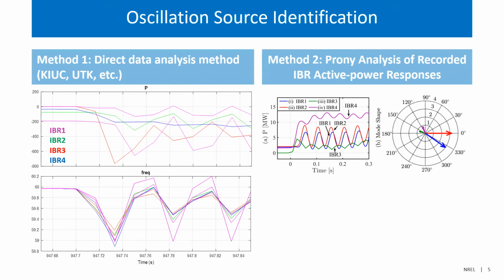They pulled the data from the digital fault recorder and tried to understand how the frequency looked like, how the power response looked like from all the IBRs. They started to analyze the data, and we found significant oscillations, and we could see IBR 1 and 2 oscillating against IBR 3 and IBR 4.